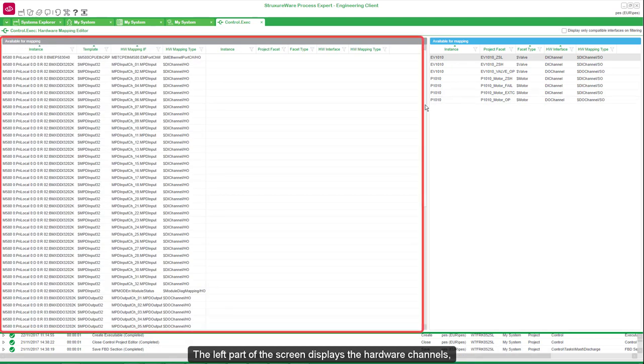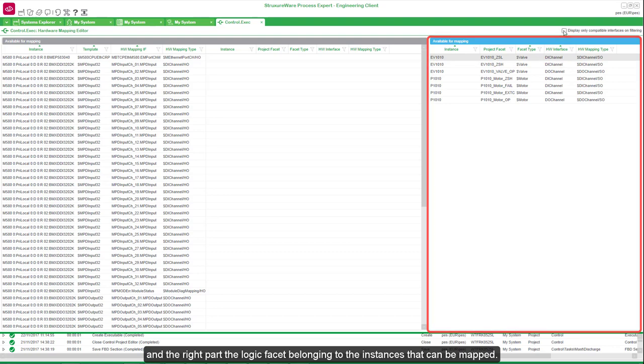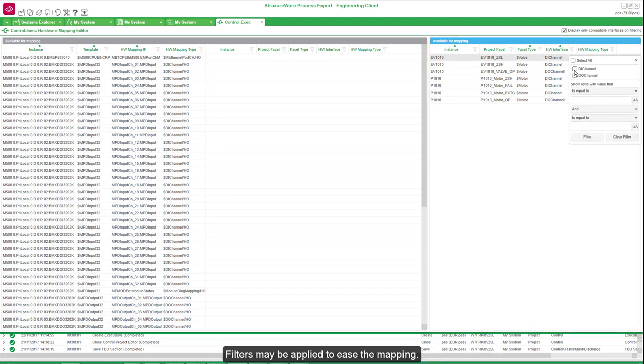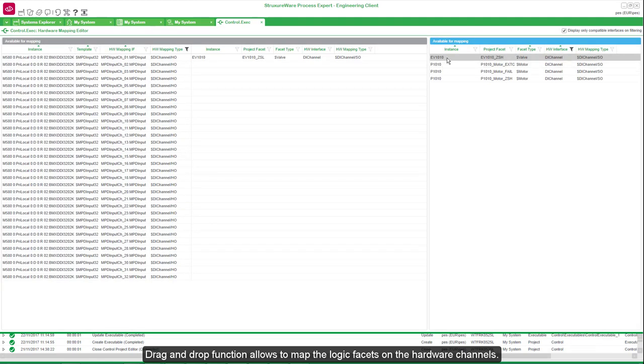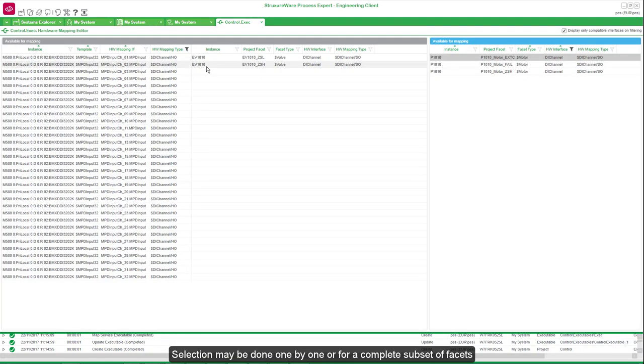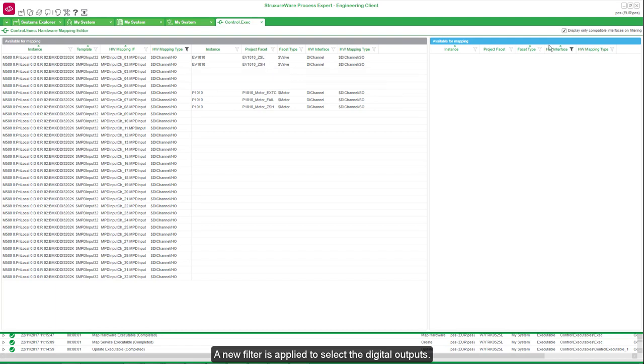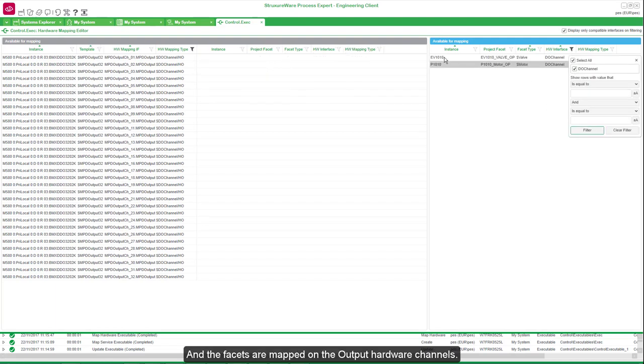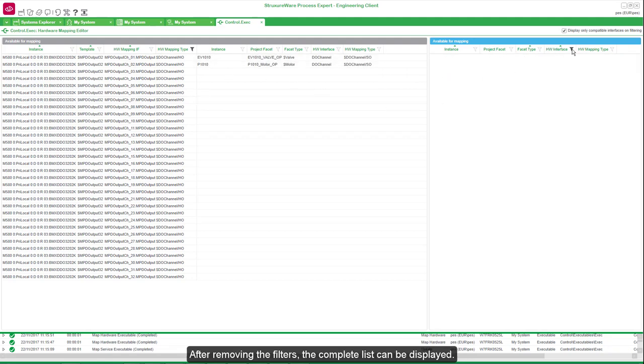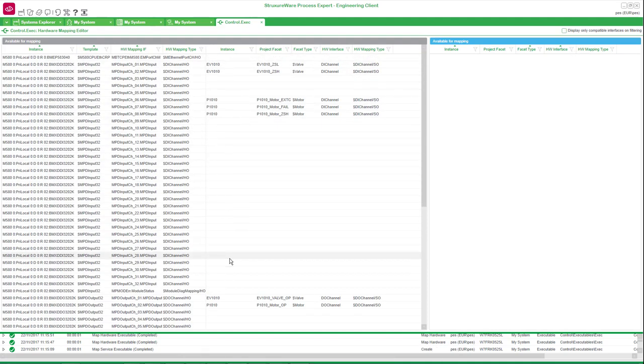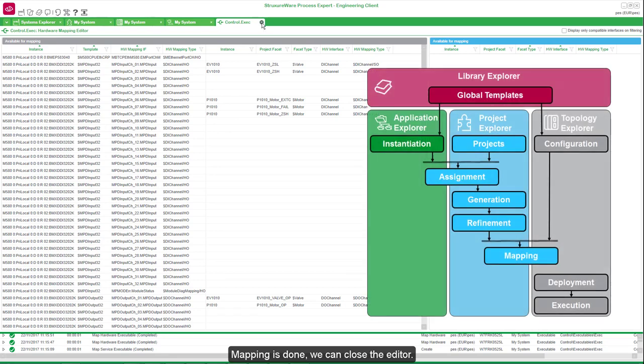The left part of the screen displays the hardware channels, and the right part the logic facets belonging to the instances that can be mapped. Filters may be applied to ease the mapping. Here we select to display only the digital input channels. Now the right side and the left side only show the facets that can match. Drag and drop allows you to map the logic facets on the hardware channels. Selection may be done one by one or for a complete subset of facets. A new filter is applied to select the digital outputs, and the facets are mapped on the output hardware channels. After removing the filters, the complete list can be displayed. Mapping is done; we can close the editor.